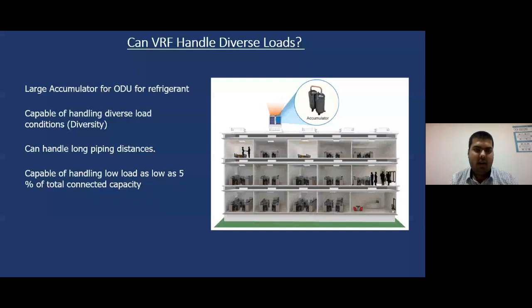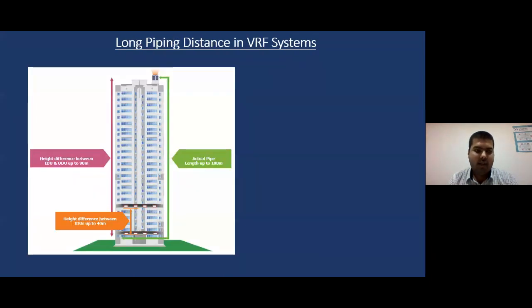Long piping distance in VRF systems. VRF systems for a high-rise building are a very good application, so that it does not spoil the entire exterior of the building. Basically, the height difference between my two ODUs is up to 40 meters. The actual height difference between IDU and ODU is up to 90 meters, and the actual pipe length between my first indoor and my last outdoor is 180 meters.